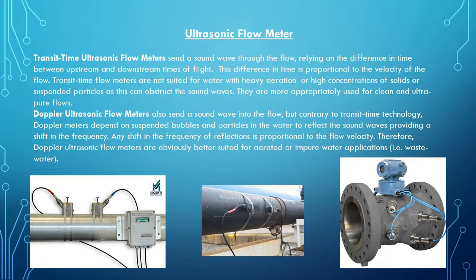Transit time ultrasonic flow meters use the principle of sending and receiving ultrasonic signals. The velocity of the liquid changes the transit time of the signals. This change in time is used to measure the velocity of the liquids flowing inside of the pipe.